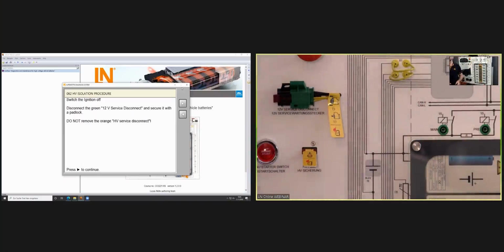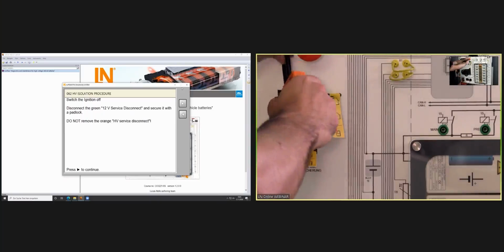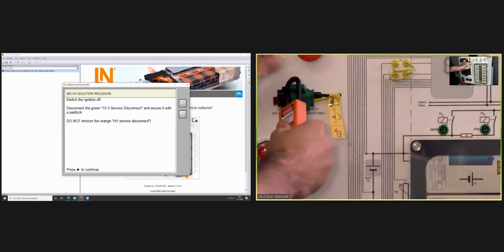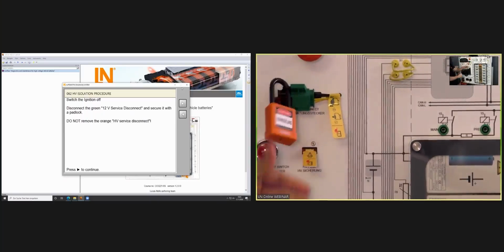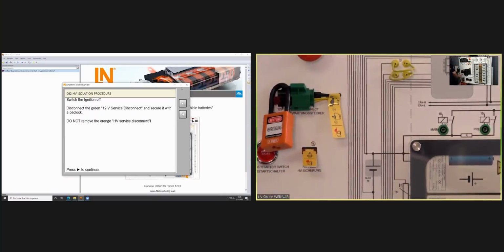And now, as I said, we need the padlock. This is what we do now. We bring it through the hole and connect it here. So that means we have disconnected the high voltage system through this low voltage disconnect, and secured it so no one else can put it back into operation as long as the padlock is here. Same as what Daniel did with the padlock key, we keep it on our person.